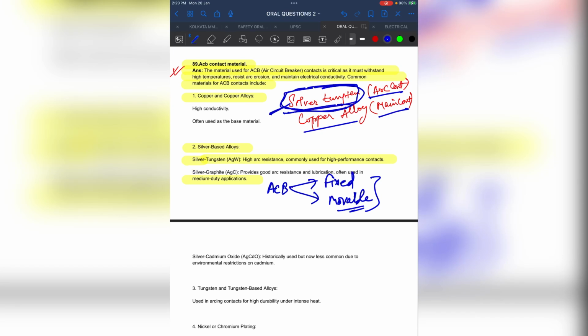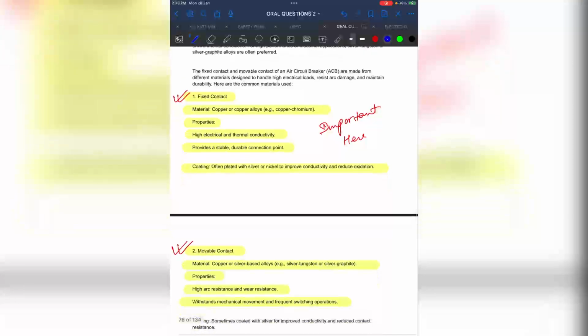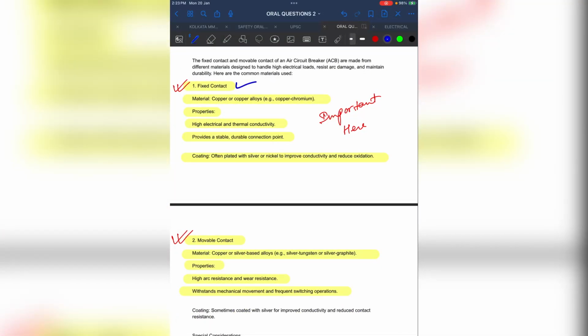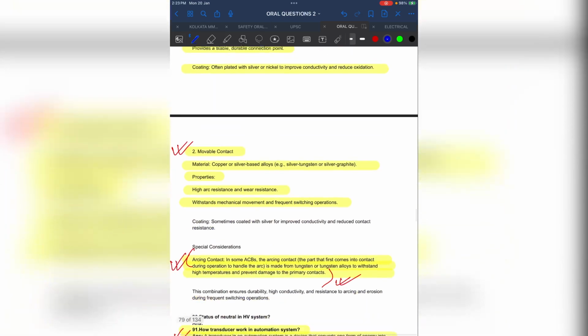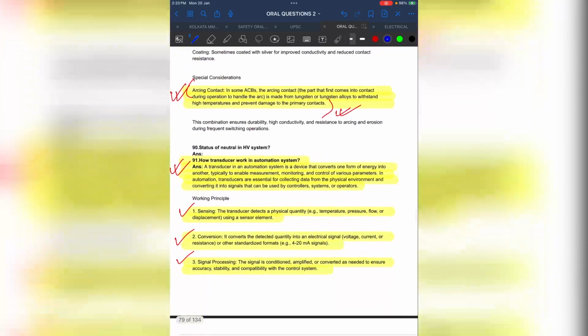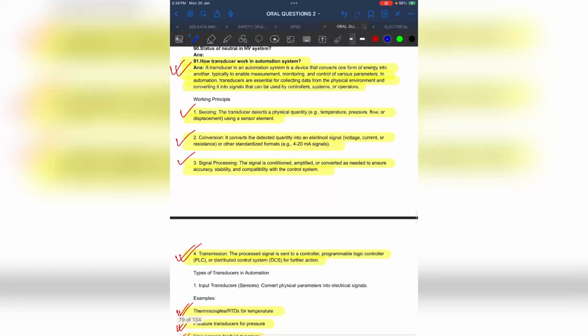This material is basically made up of silver, and the main contact generally separates first, after that the arcing contact separates at the time of opening. So the main contact carries current for very little time, and the arcing contact stays in contact for a long time and basically extinguishes all the arcs. So the arcing contact has a silver material and the main contact has the copper material. These are the materials. Here it is also written: fixed contact material copper and movable arcing contact silver. Okay, so let's go to the next question.